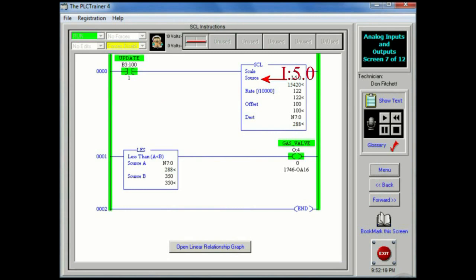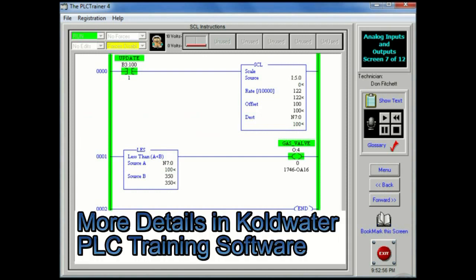SCL or scale instruction is used to scale data from an analog module and bring it into the limits prescribed by the process variable. This process variable may be either an arbitrary number or engineering units such as pounds per square inch, degrees Celsius, ounces, etc. When run conditions are true, this instruction multiplies the source by a specified rate. The rounded result is added to an offset value and placed in the destination. The equation used is: scaled value equals input value times rate plus offset.